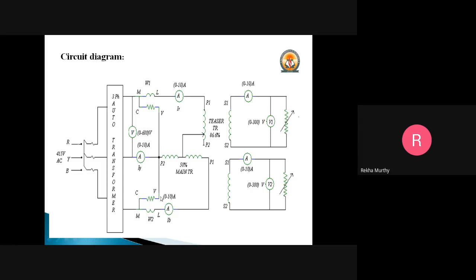Now for the second wattmeter, we've stopped at just the end of this wattmeter. Now we have to complete the loop. To do that, we again take the other end of this P1 transformer, similar to how we made the connection before. So the P1 end should be connected to the ammeter, the other end of the ammeter connected to L of the second wattmeter, and M connected back to the output of the auto transformer, that is the B phase. Then MC will be shorted. This completes the primary side.